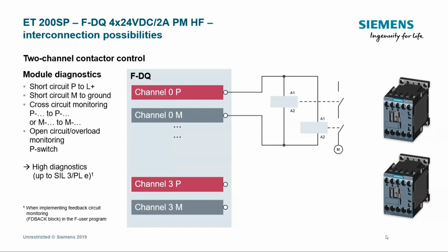Let's say to reduce the probability of failure, because the contactors have a particular probability of failure over time, and then according to the standards, there are some levels accepted that can be used for, say, a Cat 1 application, Cat 2 or Cat 3. So here the use of two contactors is actually to reduce this probability of failure to a lower level that is accepted in, say, a Cat 3 application. So that's why you see two contactors being used in parallel for this particular safety level.